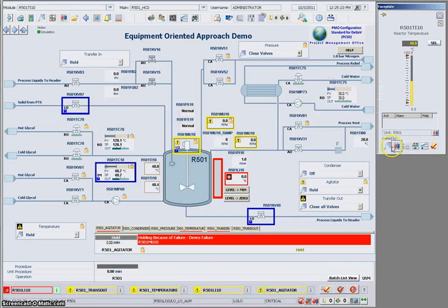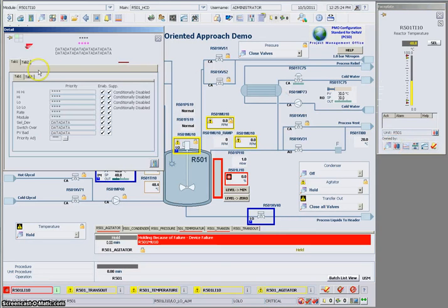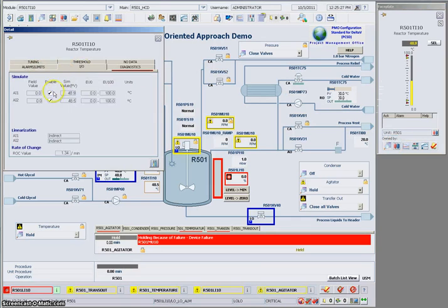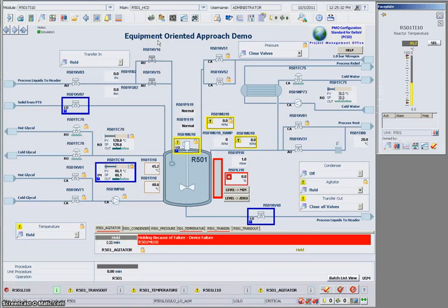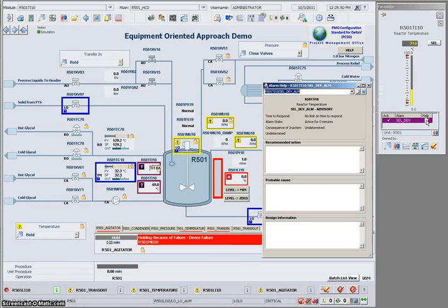First of all, let's cause another failure of our instruments. So I'm going to take one of these out of service. We notice from our human-centric design techniques that we get a new alarm, purple indicating a deviation. Selecting this, we identify there's no help over here, but we do have the little document with the pencil that allows us to author the help. Now we have the right privileges, so we can do this. Operators that don't have the right privilege will not have this option.